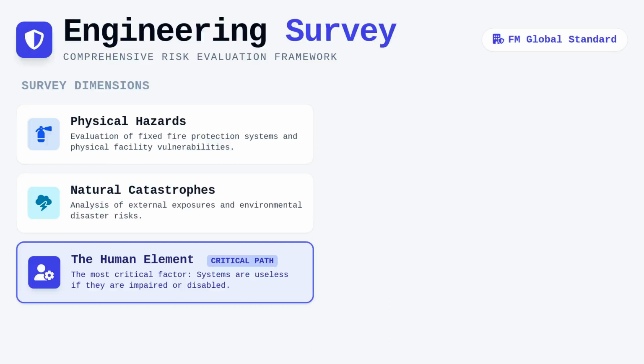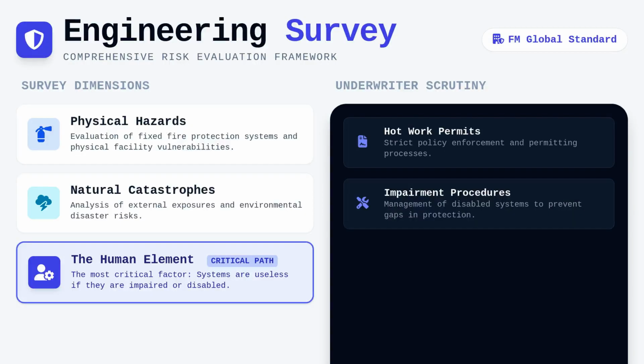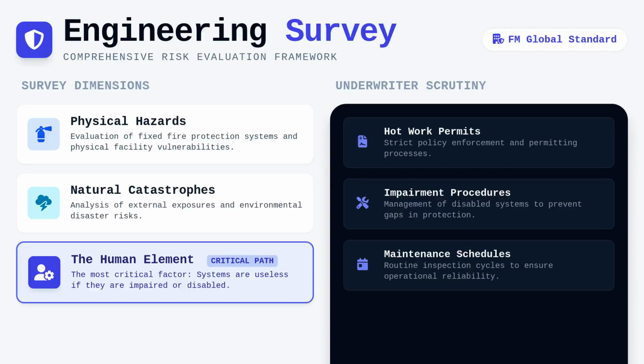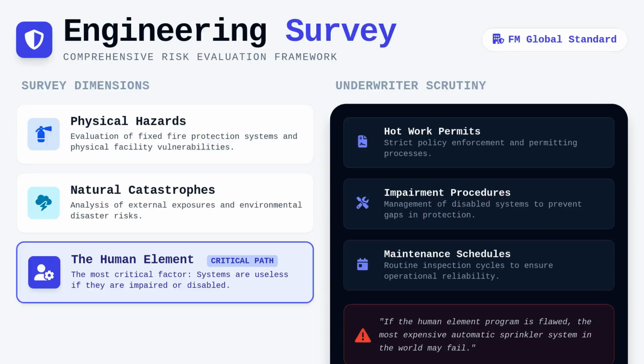The human element is often the most critical factor in these evaluations because mechanical systems are useless if they are impaired or disabled. Underwriters scrutinize policies involving hot work permits, fire protection system impairment procedures, and routine maintenance schedules to confirm that the organization is actively managing its risk. If the human element program is flawed, the most expensive automatic sprinkler system in the world may fail to prevent a catastrophic loss.